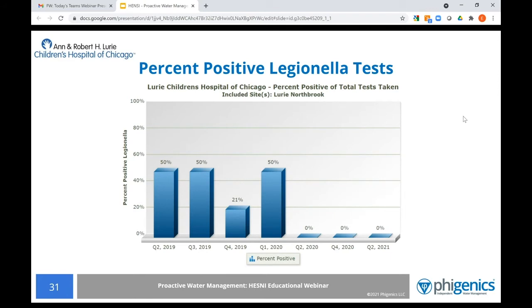All right, and here are the results of that. As Emily talked about with the validation results, we were taking actual bacteriological testing of the water at different fixtures. You can see that back in 2019, 50% of our tests came up positive for Legionella. And then right around the second quarter of 2020, when we decided we were going to start flushing the domestic hot water return, we ended up having 0 positive Legionella tests. We later automated the flushing in the fourth quarter of 2020, and the process continues today.